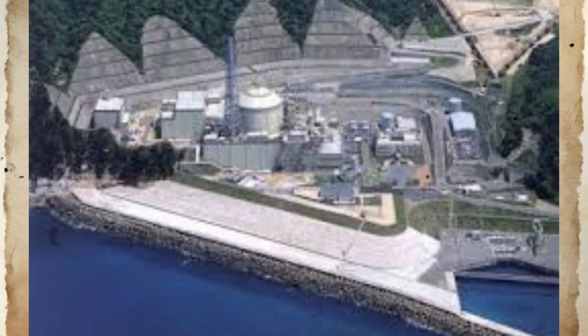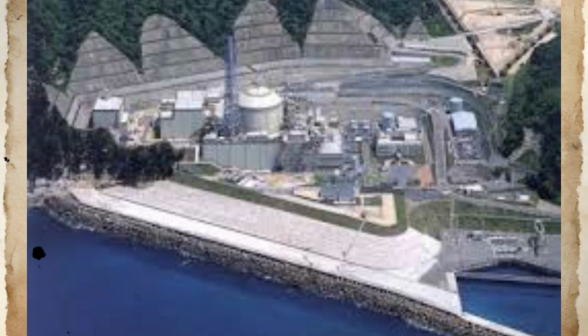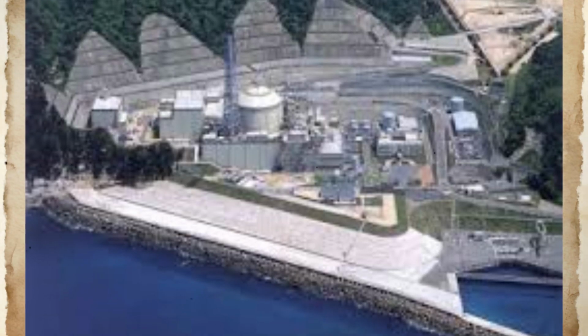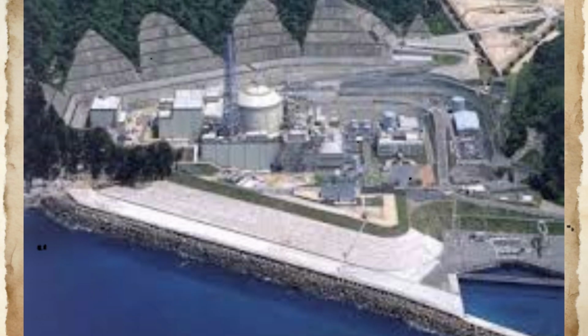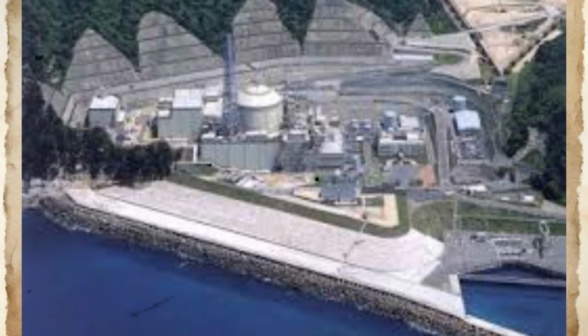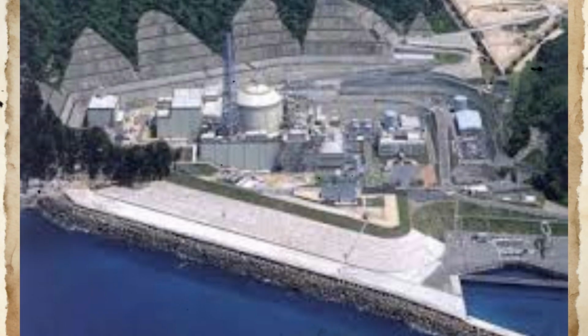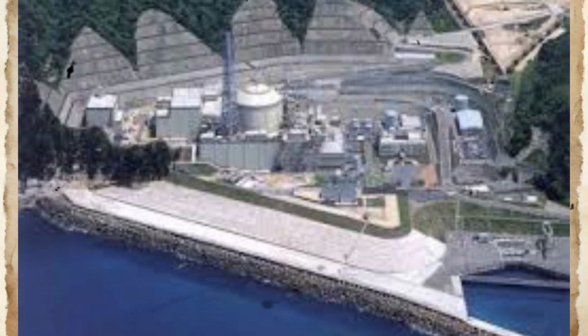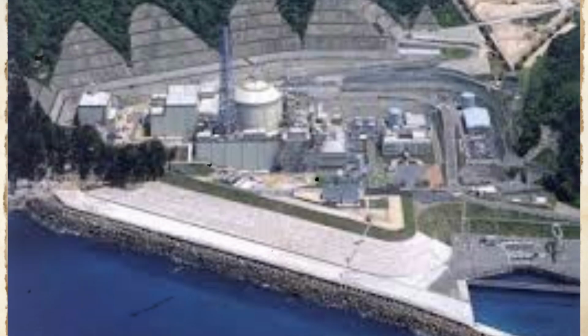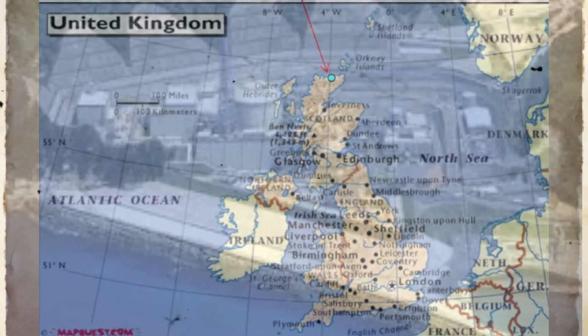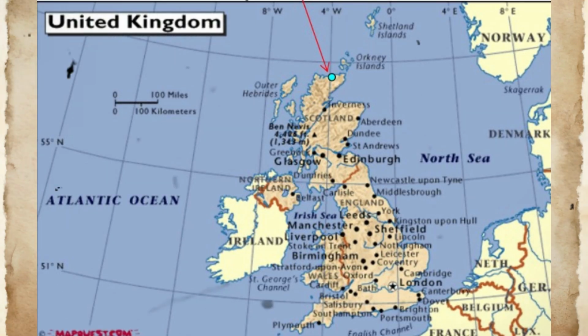Major sodium leaks would be expected to cause significant temperature variations as system inventory was lost and thermal balance was disrupted. The absence of major thermal transients suggested that the leak rate was manageable and that system integrity was not seriously compromised. Pressure measurements in SGS Loop C similarly remained within normal operating ranges. The leak flow rate was insufficient to cause detectable pressure drop in the large volume secondary loop. System pressure was maintained by the secondary sodium pumps, which continued operating normally and compensated for the small inventory loss through normal pressure control mechanisms.